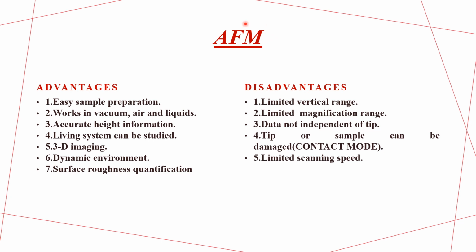Lastly, the conclusion for the atomic force microscope. Its advantages are easy sample preparation, 3D imaging, dynamic environment, accurate height information, living systems can be studied, surface roughness detection, and it works in vacuum, air, and liquid. Disadvantages are a limited vertical range, limited magnification range, data that is not independent of the tip, and the tip or sample can be damaged, especially in contact mode and if the medium is thick. In non-contact mode, the sample can be scraped, and scanning speed is limited.